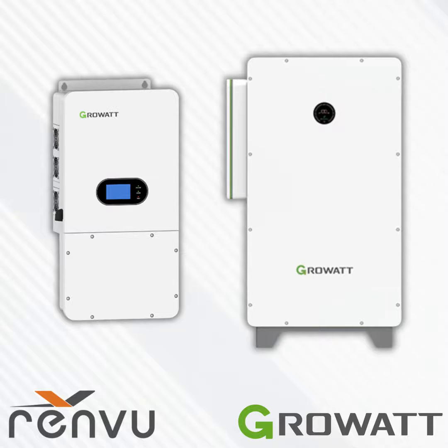However, this inverter can be put in parallel up to 6 units in on-grid and off-grid mode. So you can go up to 60,000 watts or 300 amps. Efficiency is over 97%. Charging, discharging current, 200 amps with just a single unit. And then the backup power in off-grid mode is also 10,000 watts. And then it has the built-in ATS with UPS transfer time of less than 10 milliseconds. So overall, there's a lot of features all in this one piece of hardware. It has split phase 120/240 output, as well as it's capable of doing three-phase 120/208 volt output when you have at least 2 units in parallel, which I will show on the next slide and is really what enables this product to be used in small C&I applications.